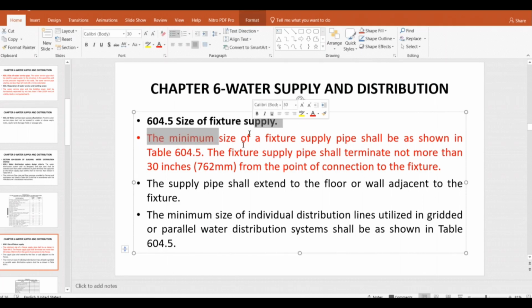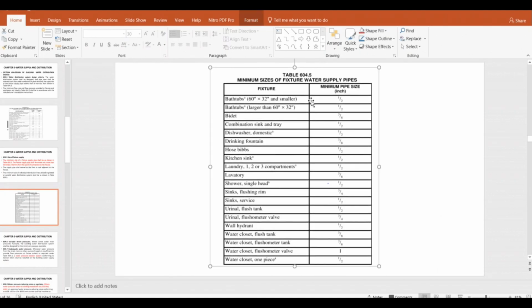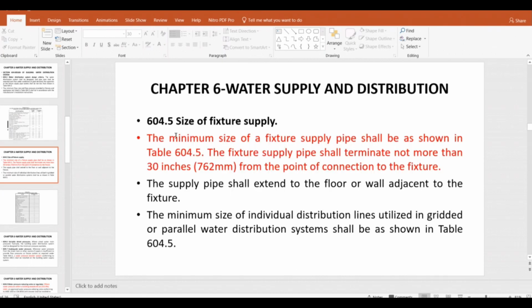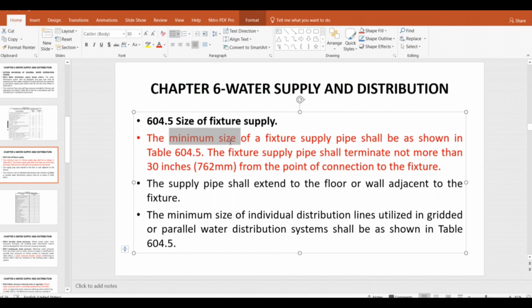Size of fixture supply: the minimum size of fixture supply pipes shall be as shown in the table. Here they have shown the minimum pipe size for bathtub, bidet, dishwasher, hose bibb, kitchen sink, laundry, lavatory, shower, and urinal. We will see that one. The fixture supply pipe shall terminate not more than 30 inches from the point of connection to the fixture. Not more than 30 inches. So the flexible connector must not be more than 30 inches from the fixture. So it has to be very close.